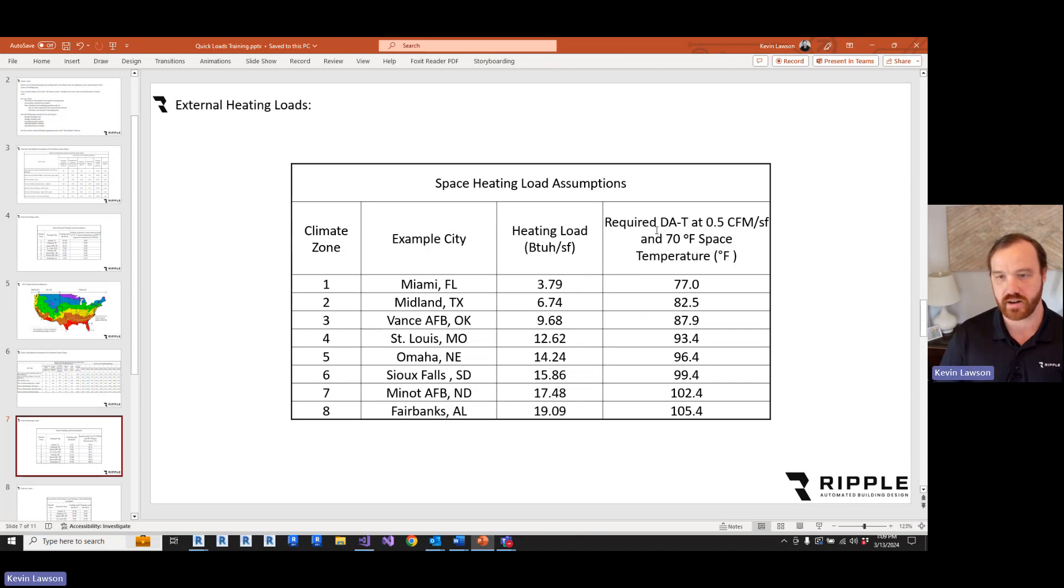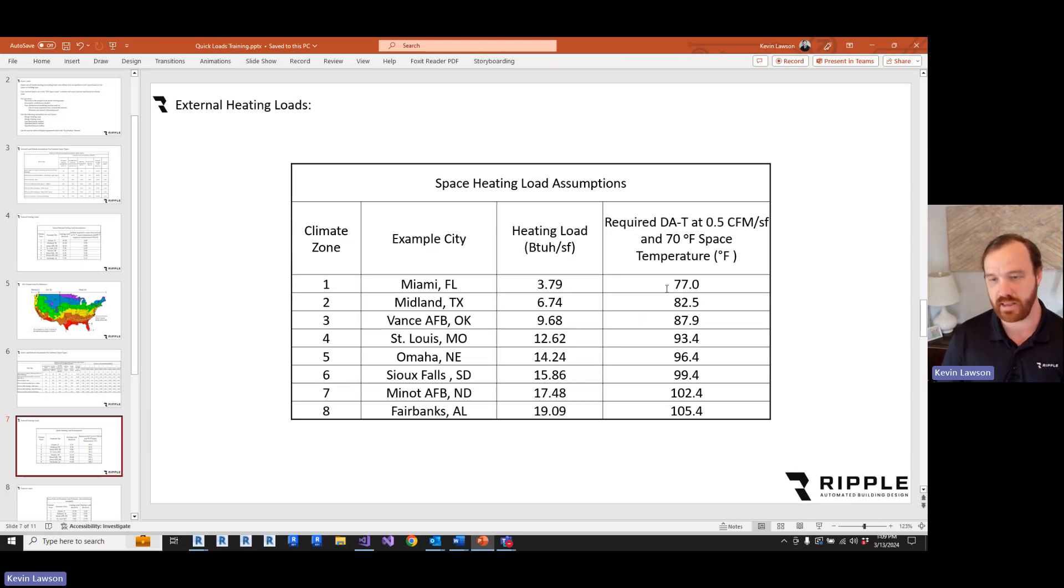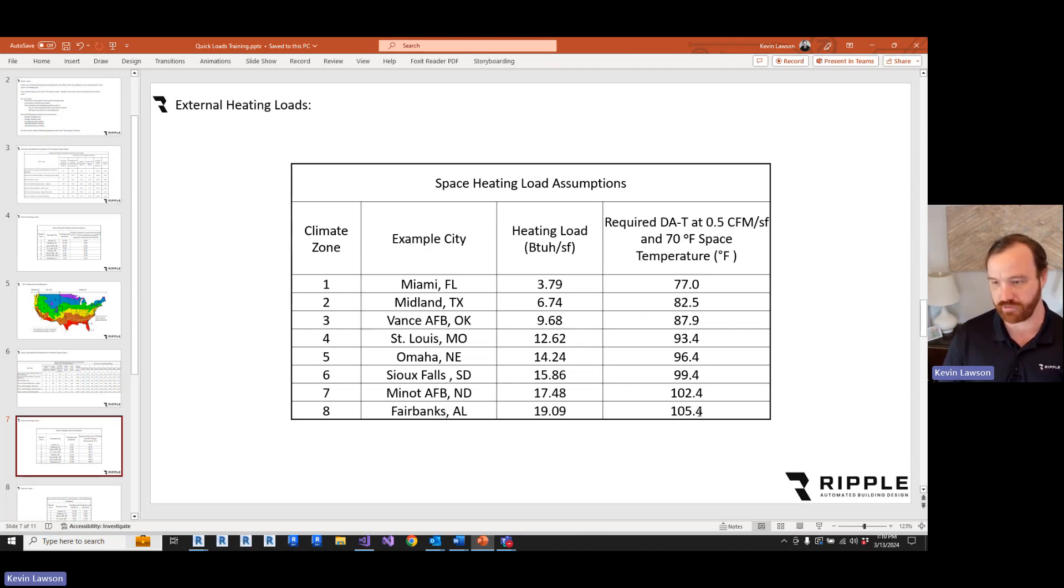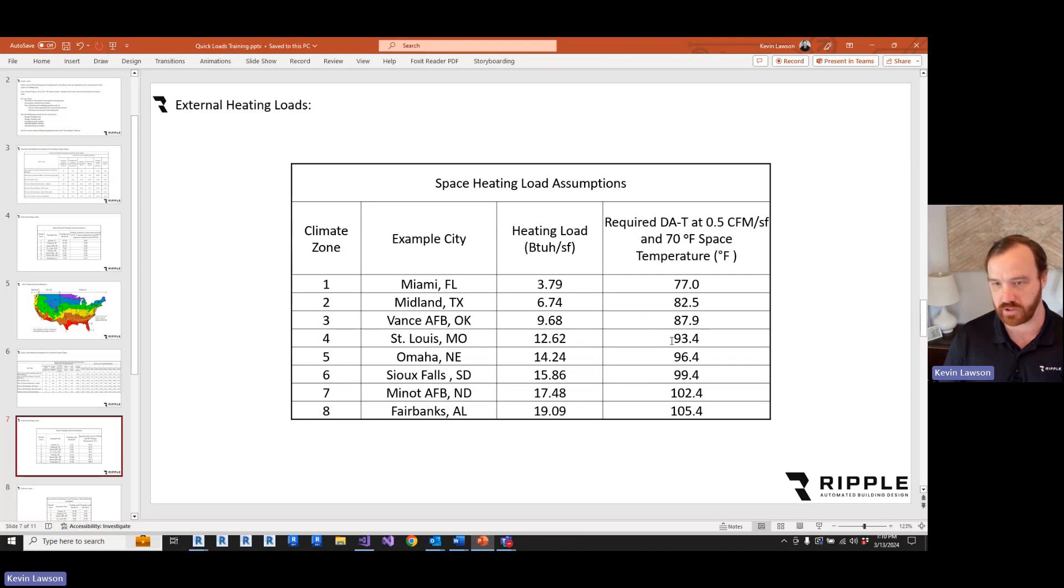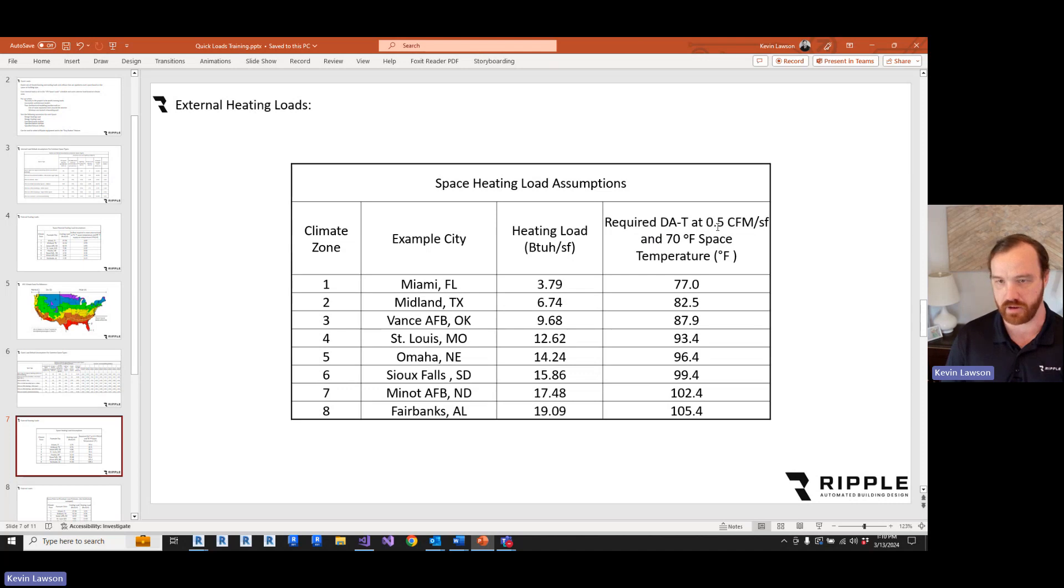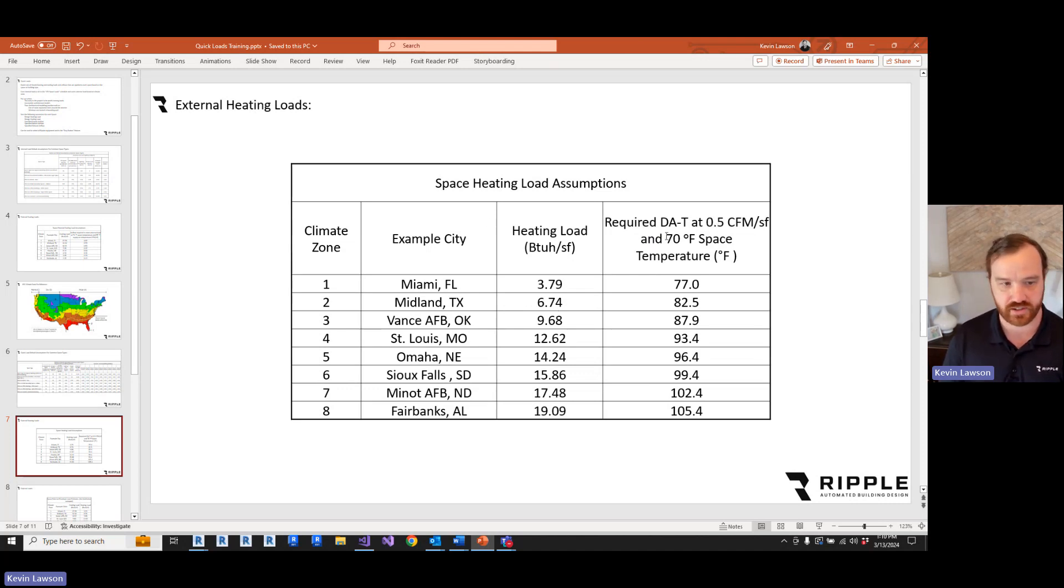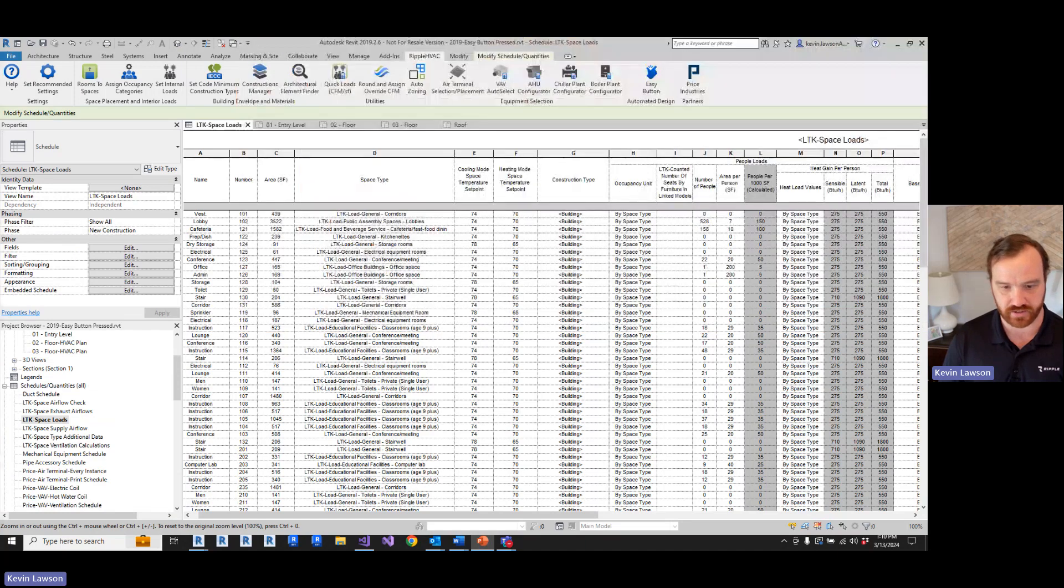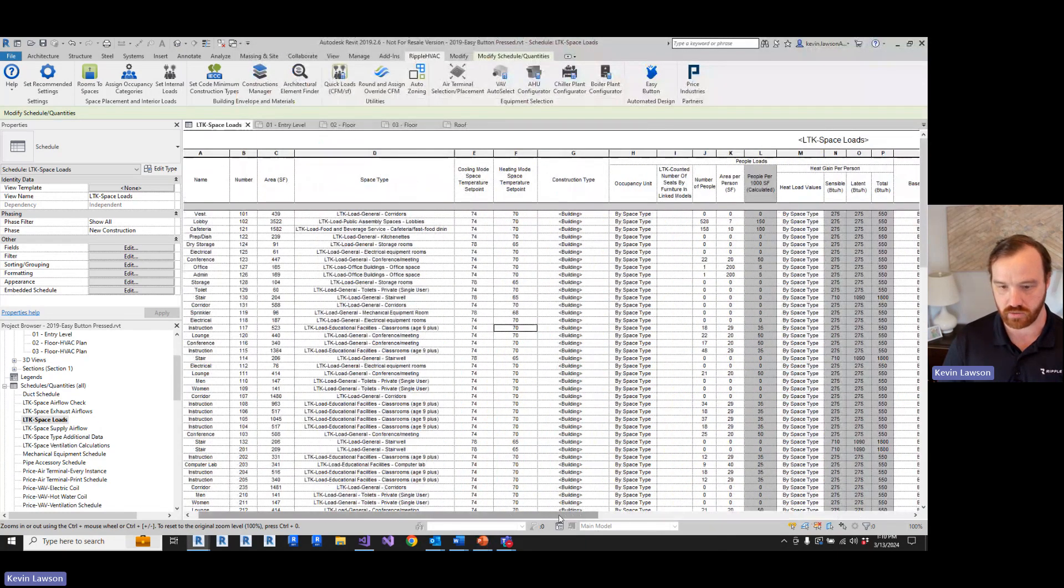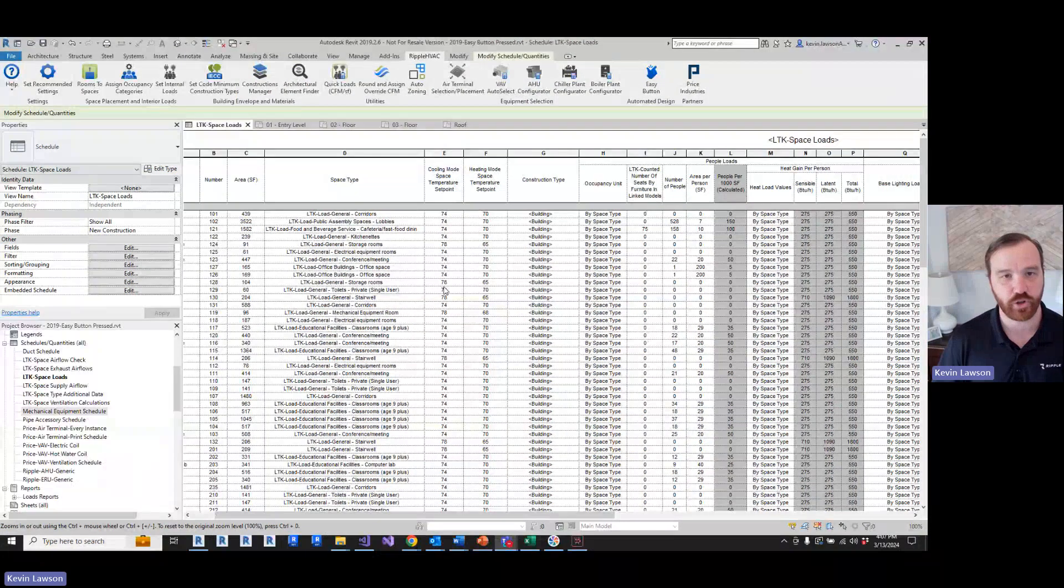The way I think about this is, if we have this load per square foot, what is the required discharge air temperature at 0.5 CFM per square foot that we would need to meet this load? So in Miami, we would need to discharge about 77 degrees. And all the way up in Fairbanks, Alaska, we need to discharge at about 105 degrees. So that gives you some idea of how much heat load this is. Now, if you want to keep your discharge air temperature under 90 degrees, you're going to have to up the minimum above 0.5. And the VAV tool handles that for you. But this is the heating load assumptions.